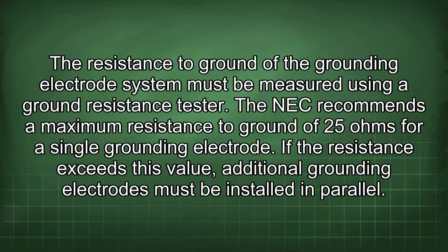The grounding electrode must be installed in accordance with the NEC and local regulations. The resistance to ground of the grounding electrode system must be measured using a ground resistance tester. The NEC recommends a maximum resistance to ground of 25 ohms for a single grounding electrode. If the resistance exceeds this value, additional grounding electrodes must be installed in parallel.